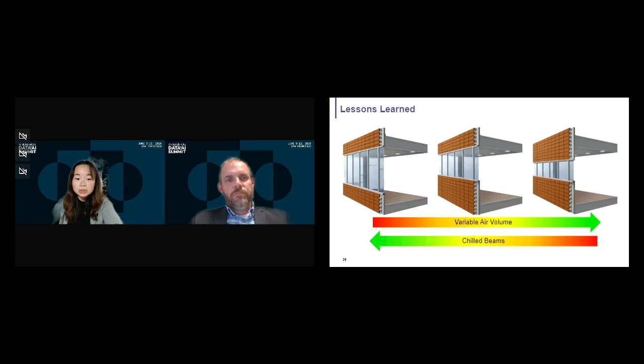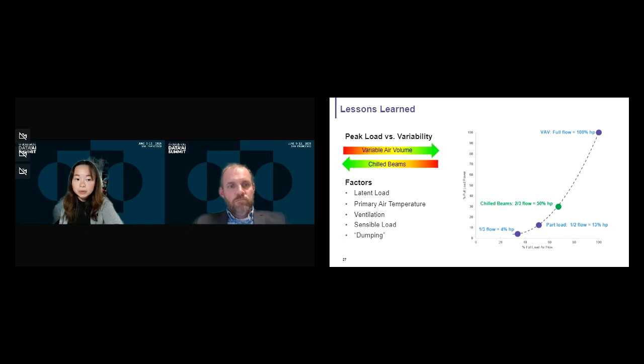Here is a graph that we further explain that phenomenon, where for a VAV system at full load condition, where it's the peak day of the summer, it consumes a lot more energy compared to a chill beam system. But as the weather become cooler in the half load or 1/3 load month around August, November, we will have a situation where having a variable air volume box is actually more energy efficient than a chill beam. So understand the local climate and designing a building accordingly became key to maximize your energy saving potential. So one of the approach we did was we also included fan power terminal units as an alternative to chill beams at certain rooms so that we can utilize the turn down of system as well as having the decoupling of cooling and ventilation.